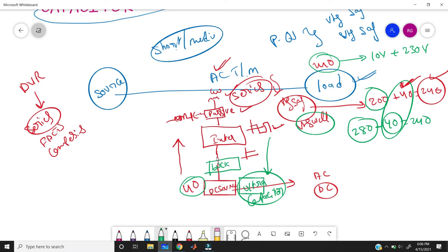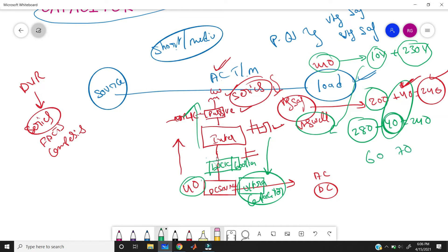To convert the 40 volts from the ultra capacitor to the required compensation voltage, we place a buck-boost converter before the inverter. In sag conditions where the required injection is large — say 230 volts — the boost converter boosts 40 volts up to 230 volts. In swell conditions where we may receive 60 to 70 extra volts, the buck converter reduces that down to 40 volts before storing it in the ultra capacitor. That is the concept of the DVR with ultra capacitor.